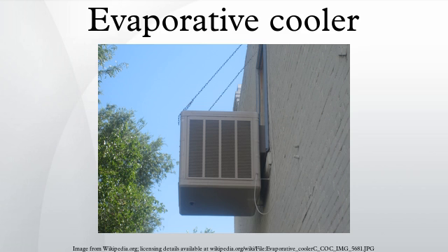This conversion of sensible heat to latent heat is known as an adiabatic process because it occurs at a constant enthalpy value. Evaporative cooling therefore causes a drop in the temperature of air proportional to the sensible heat drop and an increase in humidity proportional to the latent heat gain. Evaporative cooling can be visualized using a psychrometric chart by finding the initial air condition and moving along a line of constant enthalpy toward a state of high humidity. A simple example of natural evaporative cooling is perspiration, or sweat, secreted by the body, evaporation of which cools the body.